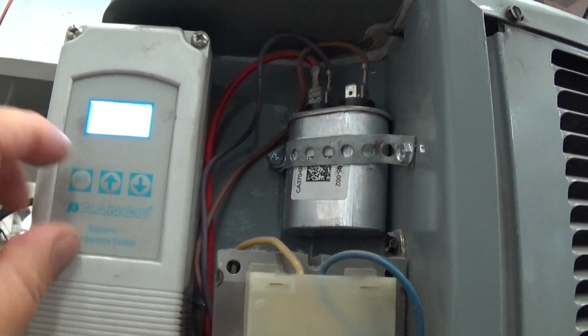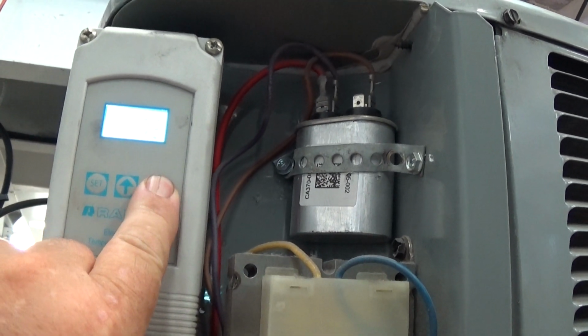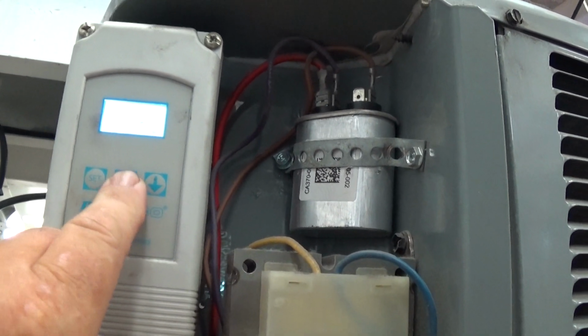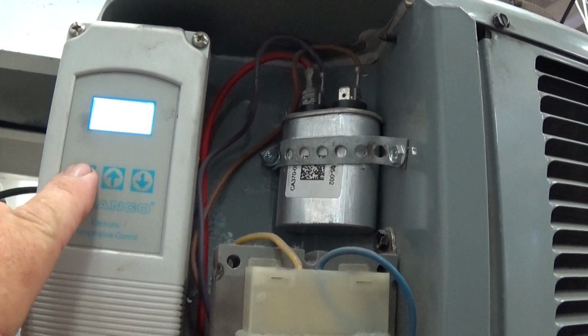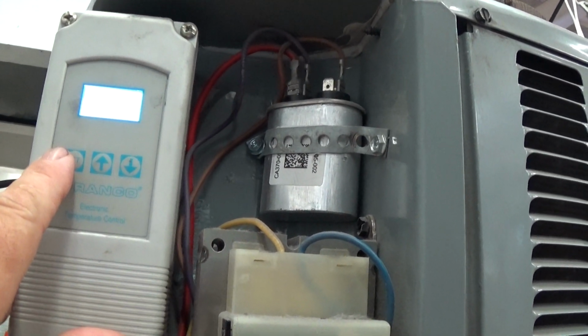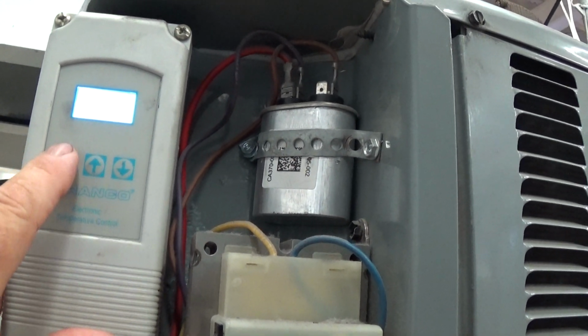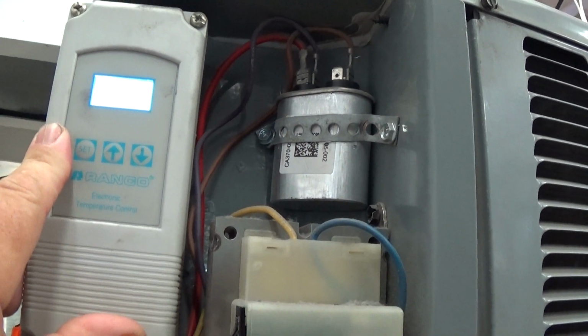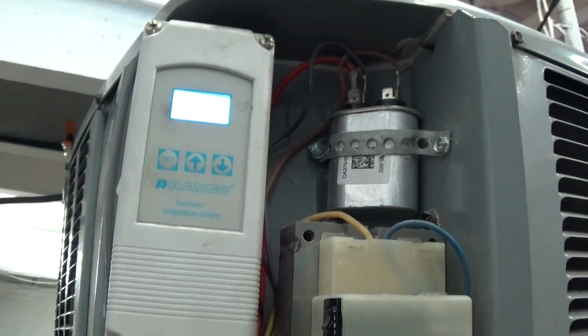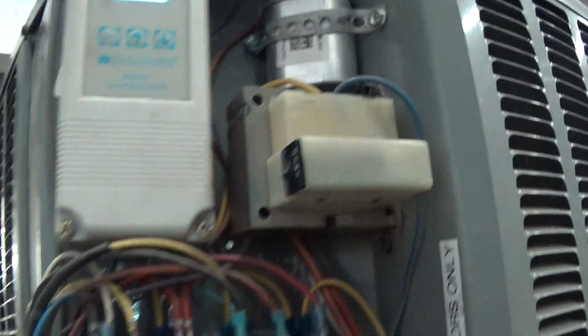Set again, Fahrenheit, leave it there. Set again, that's our set point. We're going to bring it down to, say, 52. We'll call it 50. Press set again. We currently have the differential at 3. Don't run it any tighter than that. It'd actually be nicer if you could run it a little bit bigger, depending on your process. Press set again. C1, that's what we want to leave it in for cooling mode. Press set again, and the compressor and fan just turned on, and we're chilling.